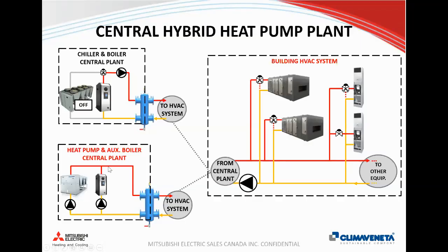If we're talking about net zero carbon buildings, this doesn't necessarily have to be a gas boiler. You could simply put in an electric boiler to eliminate carbon from the building. And in which case, if you're comparing to an electric boiler, because of the COP, which we'll talk about later, the heat pump will always make sense over a conventional electric resistive heating source. So again, the idea is just taking the heat pump central plant with auxiliary boiler and applying that into similar 2-pipe systems that we have. It sounds great in theory, so how come we don't see more of these systems around these days?